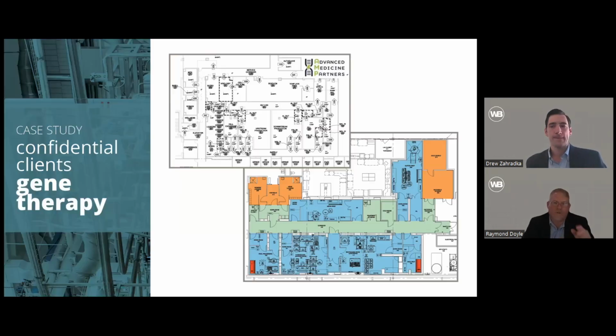Go back one sec, because I was going to answer another question, if I can interject here while you're on this slide. There was another question about velocities at the discharge of HEPA filters and how many HEPA filters you need for ceiling coverage. And it really comes down to, again, as I said, how many air changes you want to drive in the space and how you want to be able to maintain or measure that particle count of bacteria or live cell count. So the standard really defines that you do it between 70 and 105 feet per minute. But what that really drives is the number of HEPA filters you're going to have.